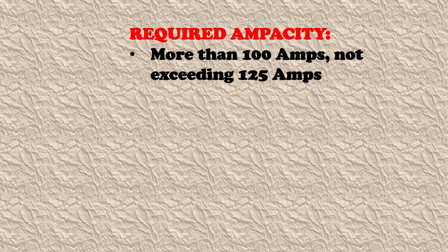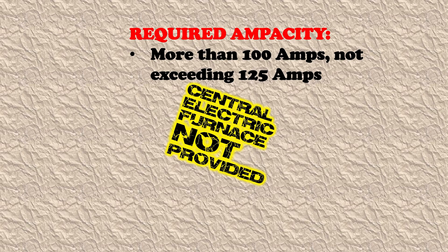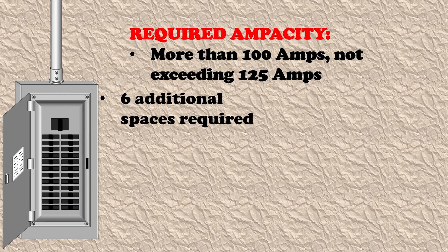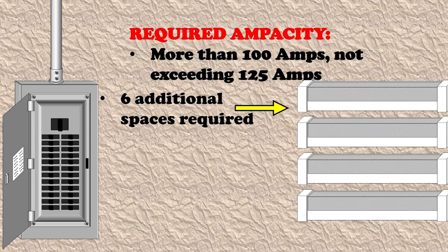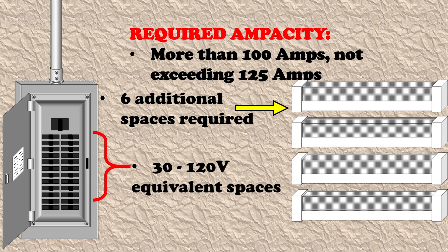Our next example has the same required ampacity range — more than 100 amps but not exceeding 125 amps inclusive — but in this case a central electric furnace is not provided. Because a central electric furnace is not provided, we are now required to have six additional spaces, since we no longer have that two-pole breaker supplying a central electric furnace. This could be something like baseboard heaters individually in each room, requiring a bit of extra panel space. In this case, we are required to have 30 of those 120-volt equivalent spaces.